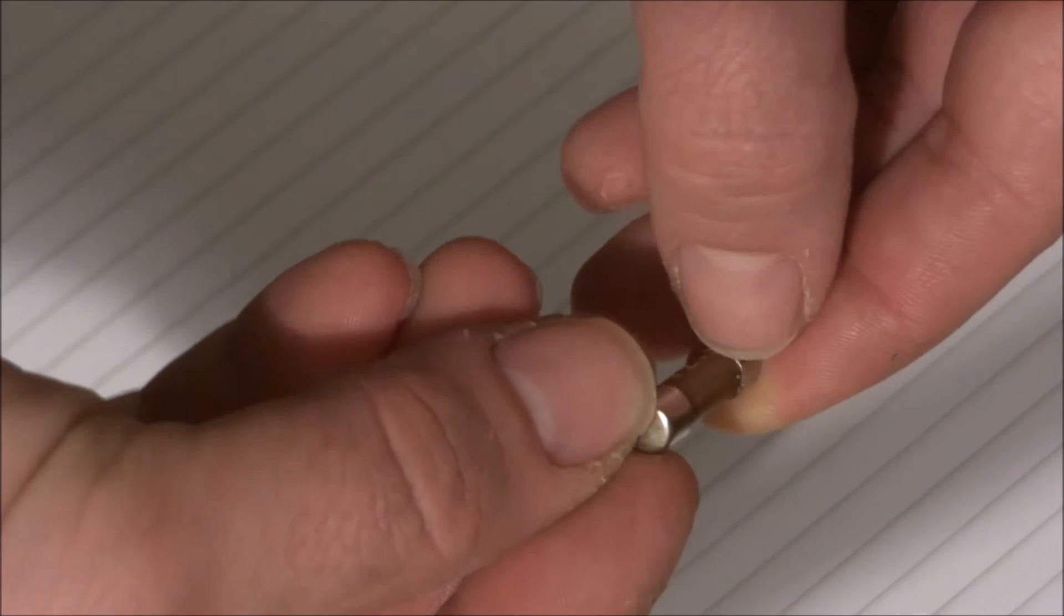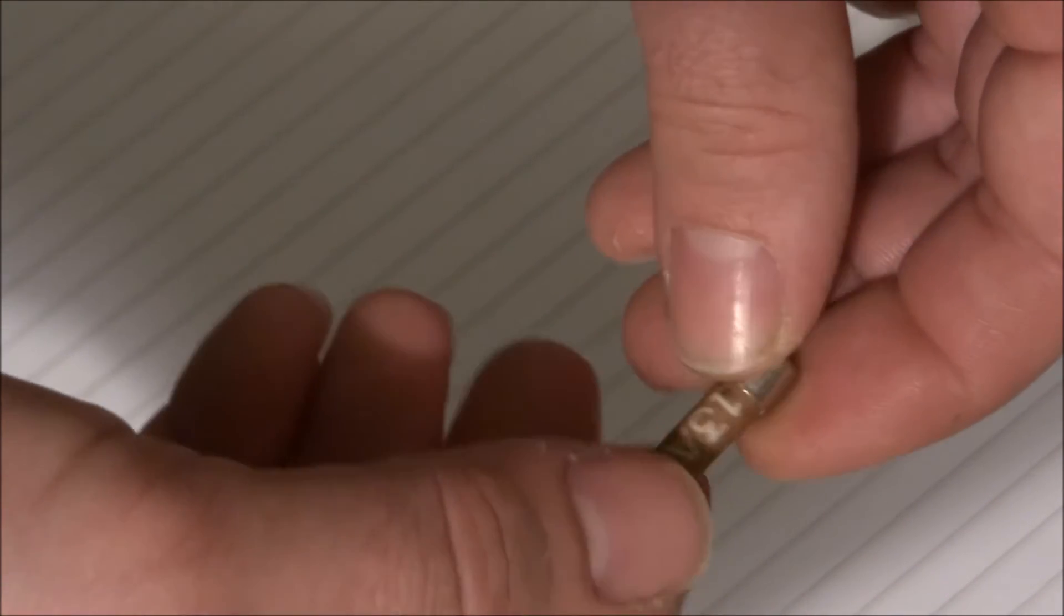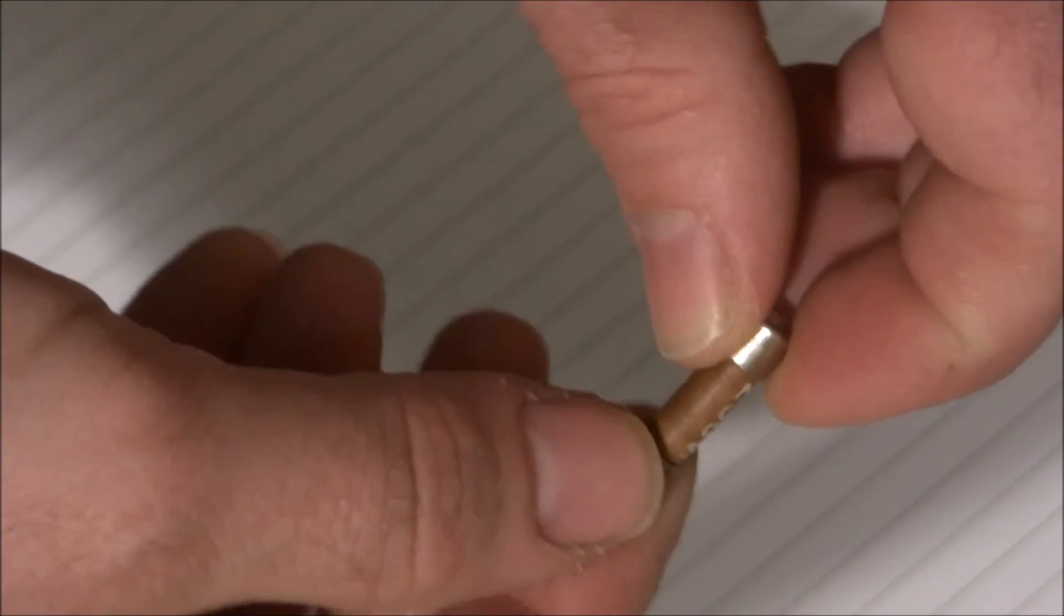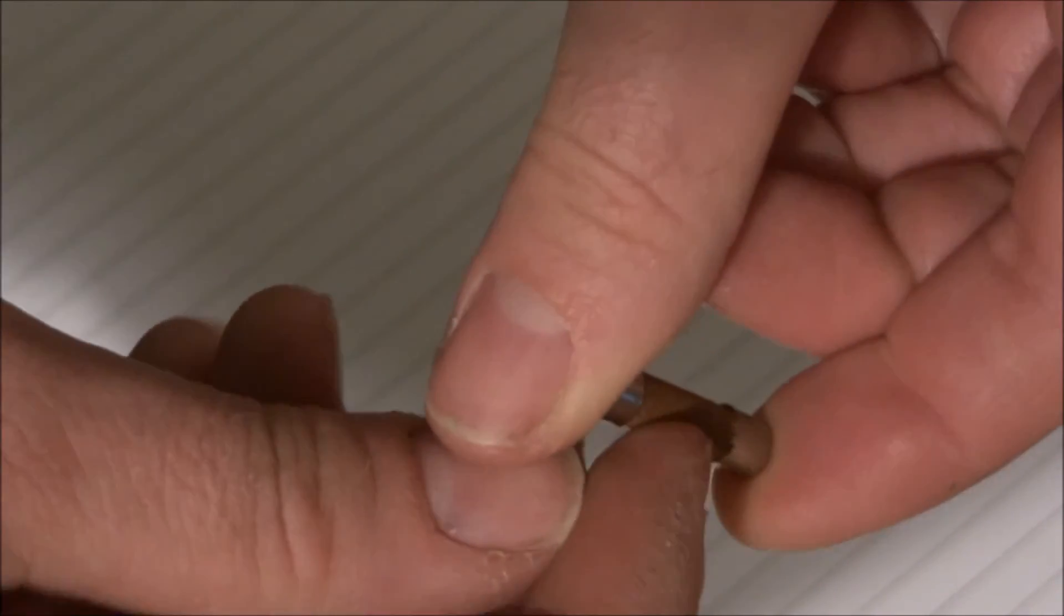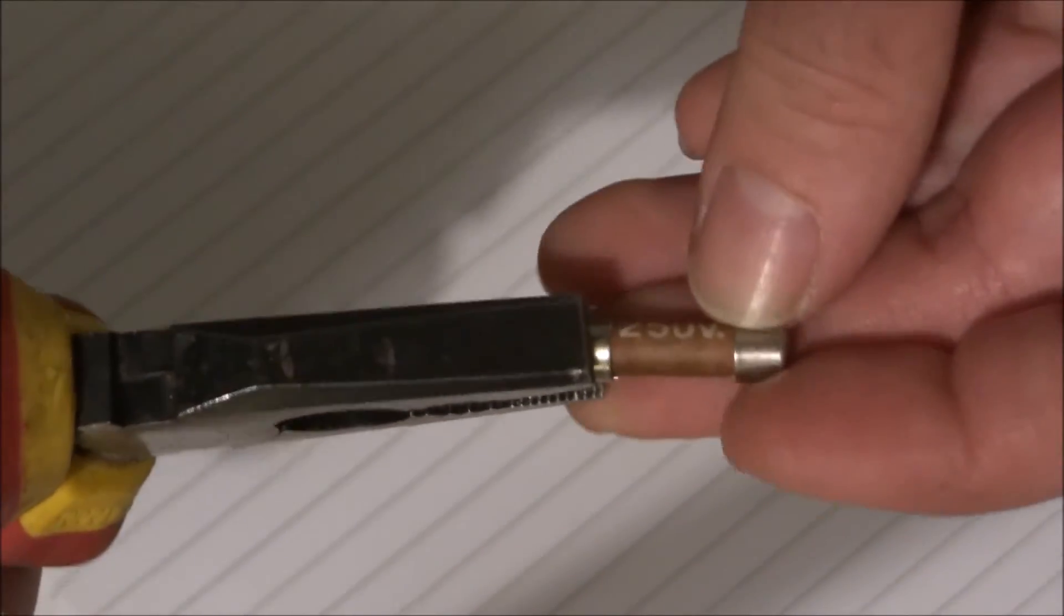I've seen other non-compliant fuses of this era and they are slightly better made than this. In particular, they don't have the fuse wire sticking out. You can probably just see in this camera, small bit of fuse wire there, small bit of fuse wire there - it's just bulged under the caps. Some older fuses I've seen this on, although generally I see it on fake ones, which leads me to believe that this whole contraption probably came from the Far East even back then in the 1970s. All fuses should have the fuse wire internally soldered in the middle of each pin end cap and strung straight across the middle suspended in sand, and this clearly isn't. This is clearly just wrapped under, and it's probably going to fall apart. The reason we have sand in them - you can read up on that elsewhere - but they should have sand in them. I bet this doesn't.